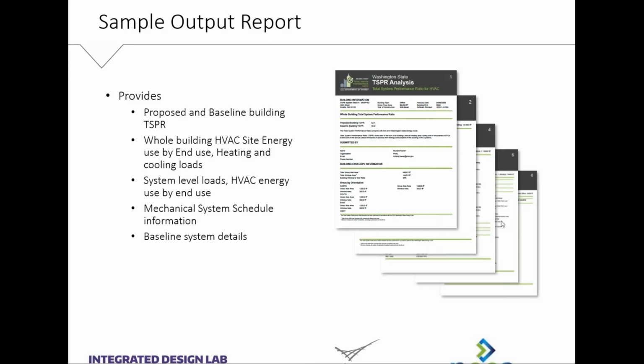The tool also generates the same information for each unique system type in the building. So you'll get the system level loads and HVAC energy used by end use for the different systems. For example, if you have a building with a rooftop heat pump and a rooftop gas furnace, and at a building level you do not meet the code requirements, the proposed TSPR is lower than the baseline, the tool will tell you what the TSPR for the 2 individual systems are, both the heat pump and the rooftop gas furnace, and you can then see which system needs to be improved in order to comply with the code requirements.